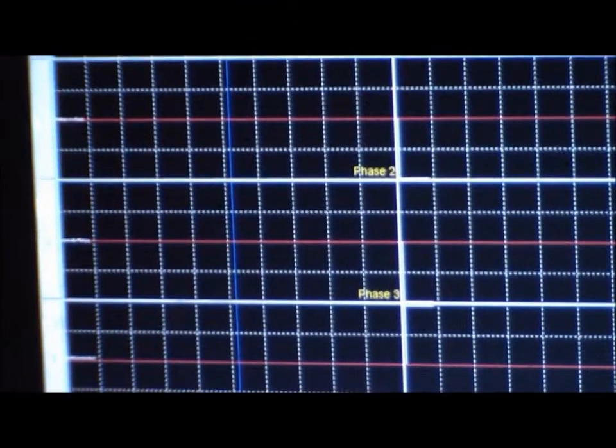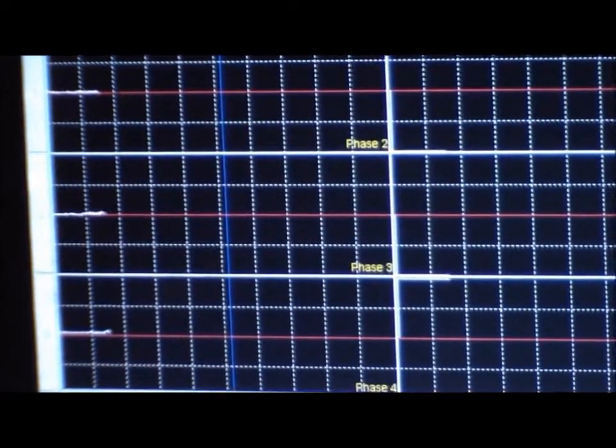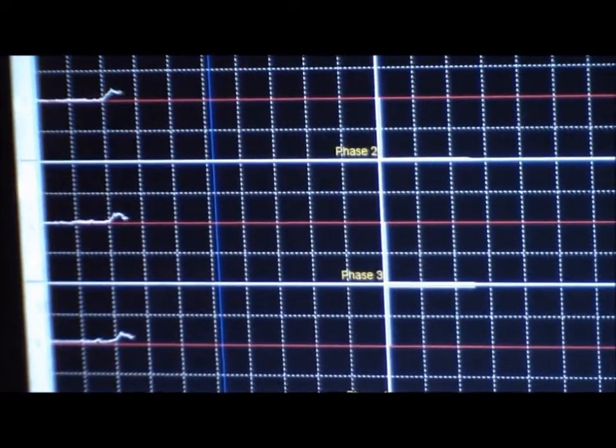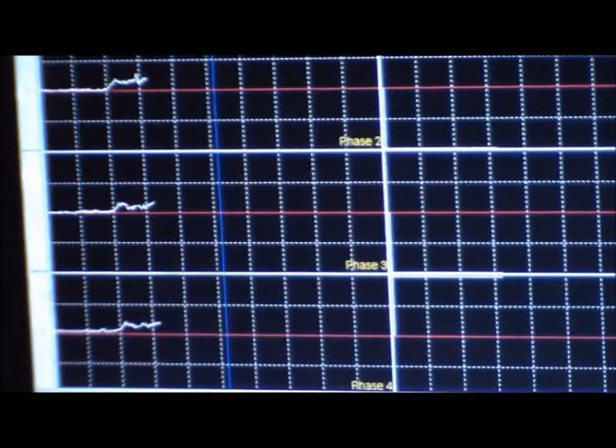Shown here is the computer screen during the scanning of a tube. The technician is looking for a significant drop in the signal, which is due to the magnetite deposit absorbing the electromagnetic signal.